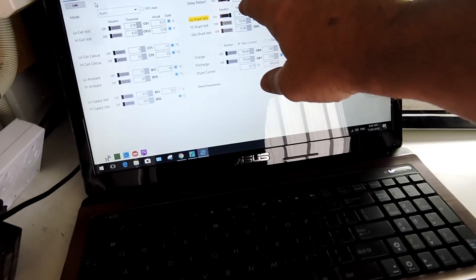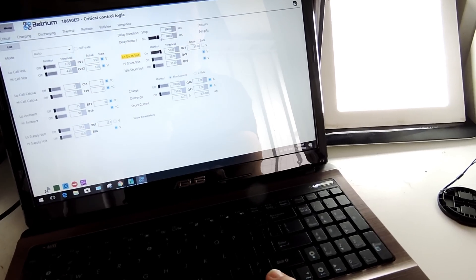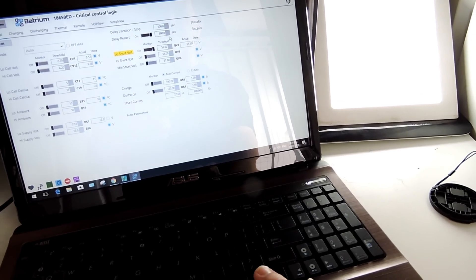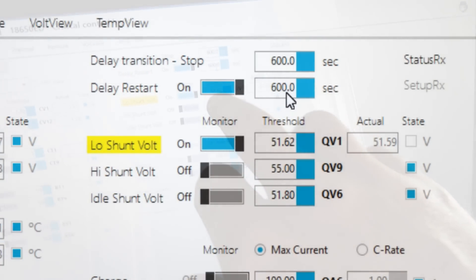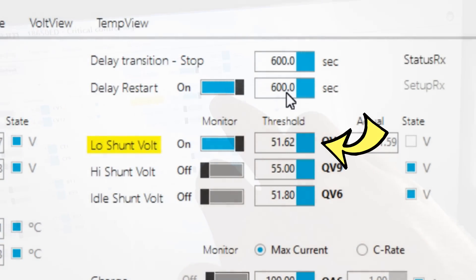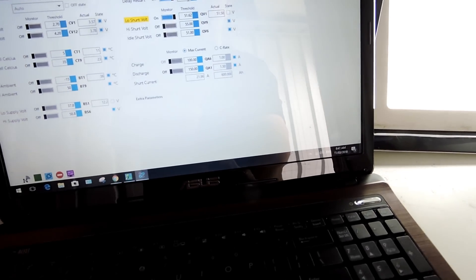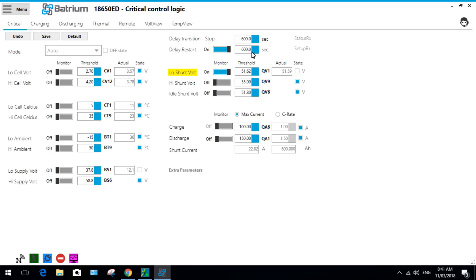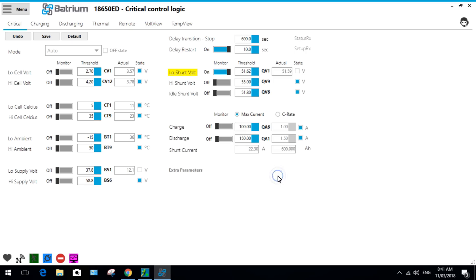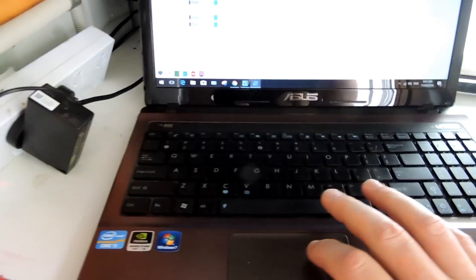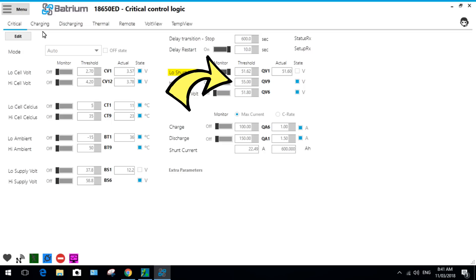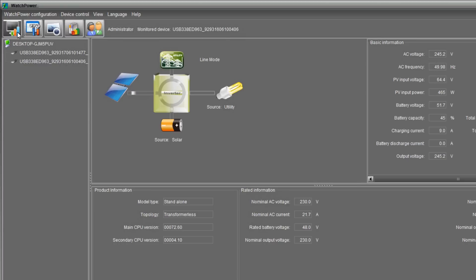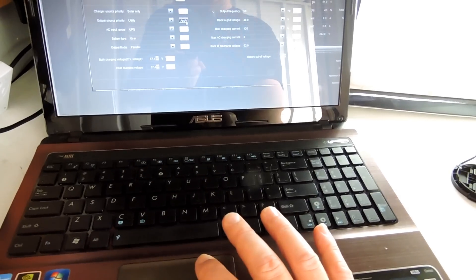Now the more important part is you've got to worry about these two figures here - delayed restart. At the moment I've got that set to 600 seconds, so it's got to wait 10 minutes. It's got to go past this figure here for more than 10 minutes before it'll actually change its state. We want to set that to say 10 seconds just for the sake of getting this to work. Now we go save. We've got to get the voltage above that voltage, so what I'll do is go down and turn off my inverter. Change it to Utility, apply - you hear a little click.